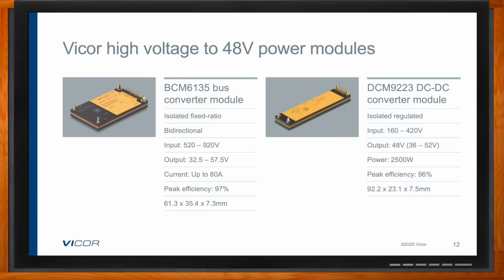On the other side, we talk about the isolated regulated solution. Here you have what we refer to as a DCM 9223, and those numbers are actually the footprint dimensions. DCM stands for DC to DC converter module. This takes an input of 160 to 420, which matches up nicely with the power factor corrected AC front ends we talked about earlier, and produces a regulated 48 volts that can be trimmed between 36 and 52 if needed. The power level is capable of 2,500 watts, and peak efficiency is 96%, which is very impressive in the industry.